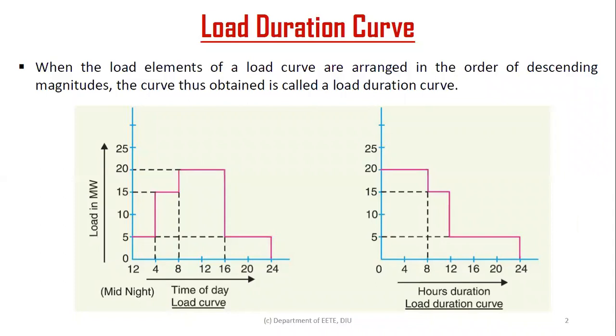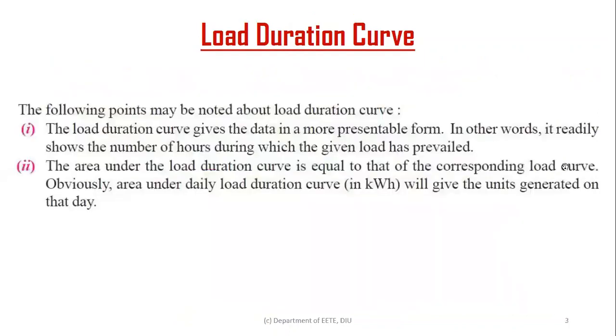So basically this was the load duration curve, quite similar to the load curve, just the way of representation is a little bit different. The load duration curve gives the data in a more presentable form. In other words, it readily shows the number of hours during which a given load prevailed. I said how many hours of 15 megawatt, how many hours of 20 megawatt, how many hours of 5 megawatt, it can give instant data.